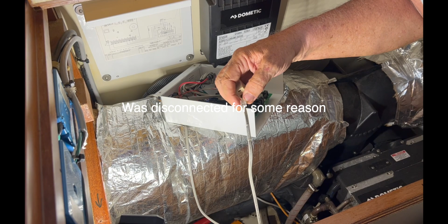Earlier I showed the box with the temp sensors for the air handlers and also for the chilled water in the 2 VARCs, the chillers. We've done the air handlers, now I've got to go into this VARC, this variable speed chiller, and get access to the probe to replace it. To do that, I have to take this panel off, take the fan off, then take the top off, then unscrew and get access inside the chiller. That's going to be quite an exercise.